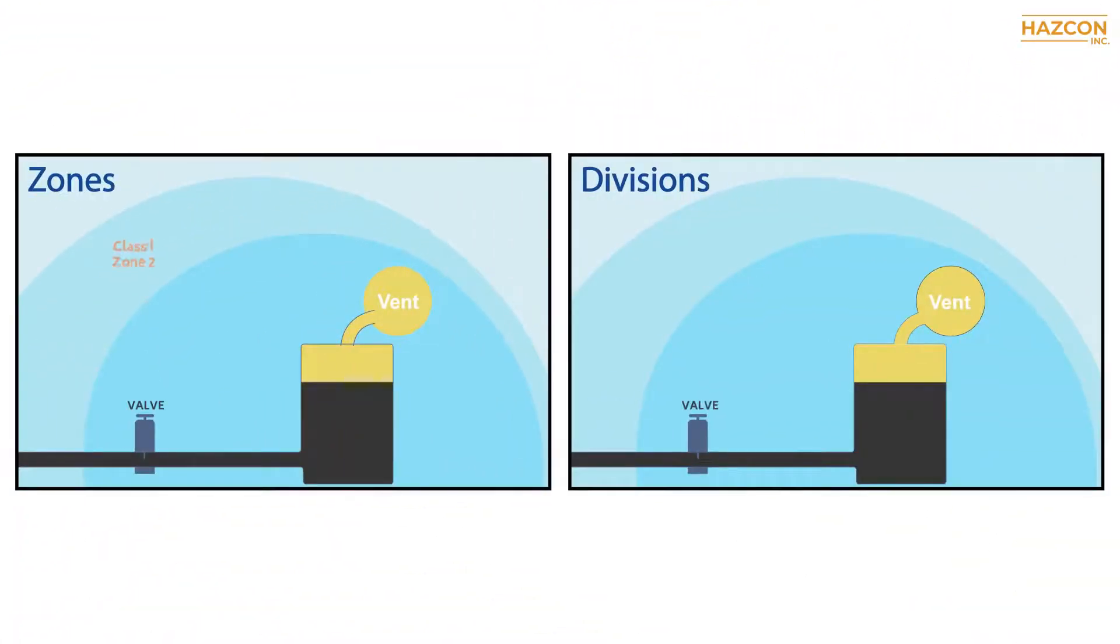The following drawing shows the relation between the two different classified systems for products approved for use in gas explosive atmospheres. First, let's start with products having class division marking.